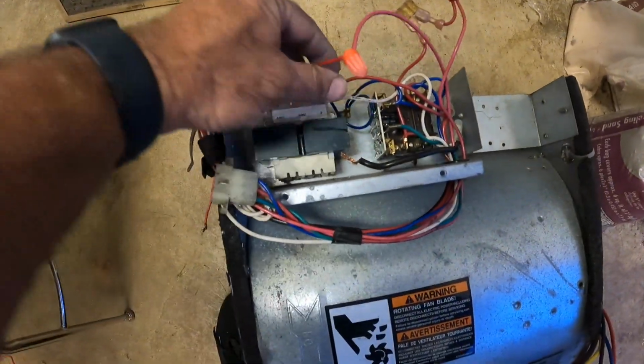One thing to be aware of when you're at a place that has three-phase power like they do here is to make sure that you use the right voltage tap on your transformer. You can see this one's on the 200 volt tap instead of the 230 volt, which means they have 208 volt here, chances are.